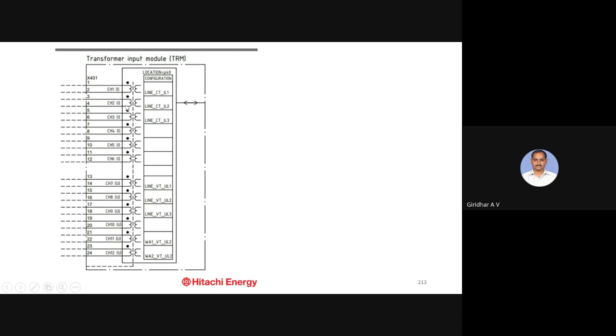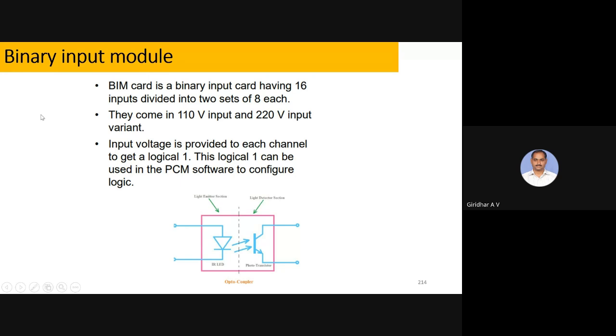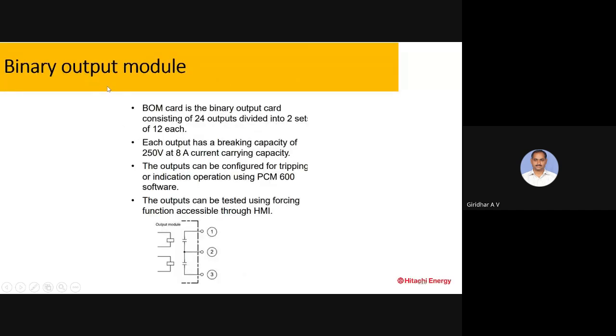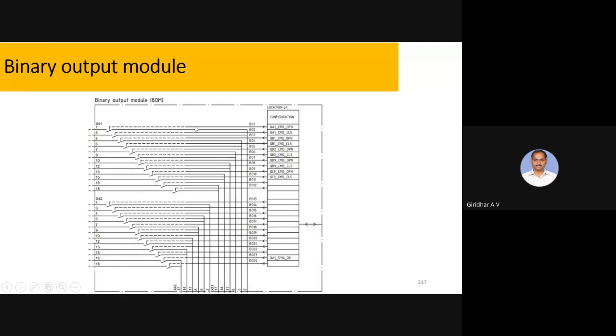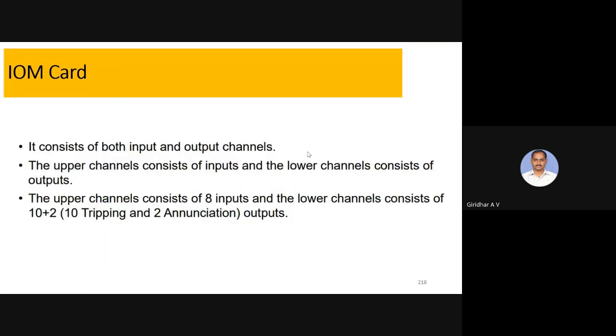Suppose these transformer input modules are connected. So binary input modules. Can you see the optocouplers they are using to get the data? So these are the binary input modules in typical IEDs. Likewise, binary output modules will be there, so the various output modules appropriately send the control actions, everything.